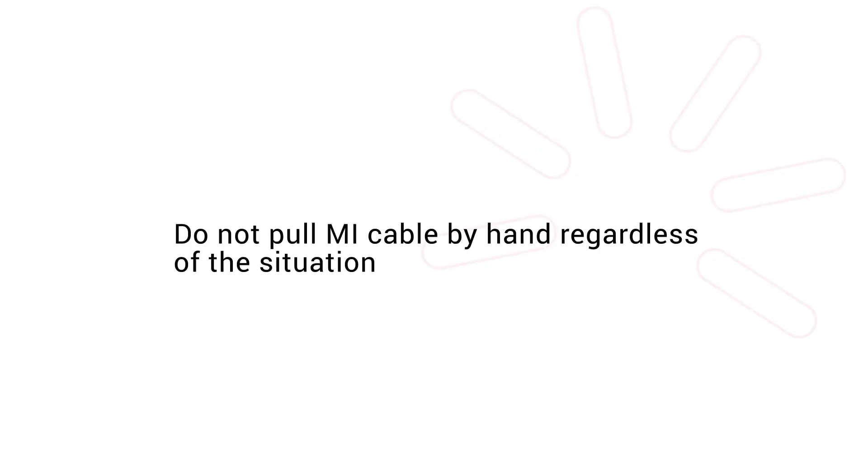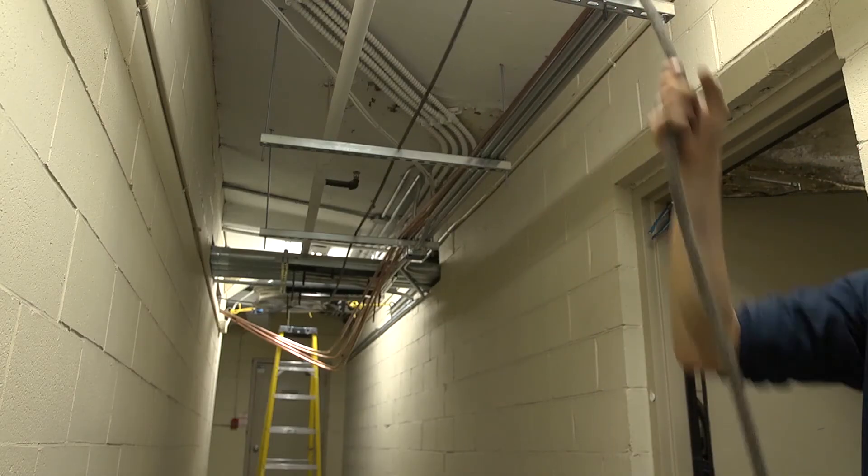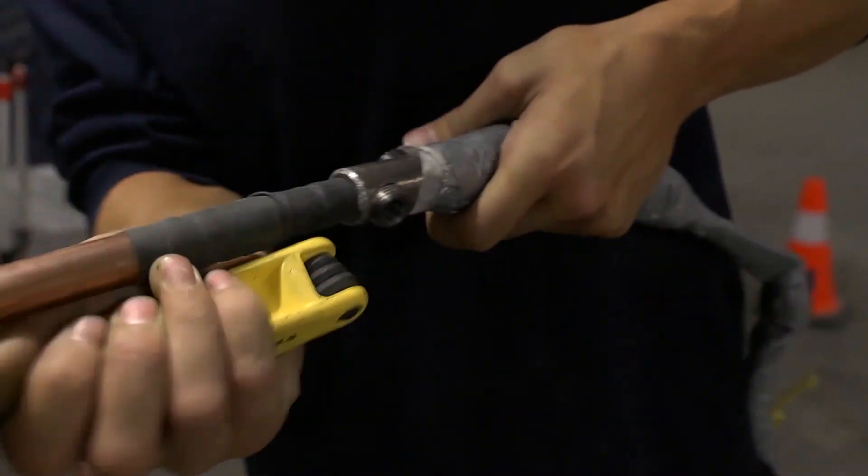When it comes to pulling MI cable, you need to make sure the proper setup has been completed. You can go back to the previous section of this video to see a step-by-step guide on how to do that. nVent does not recommend and strongly advises against pulling cable by hand no matter the scenario. Doing so will make the cable pull extremely difficult, if not impossible, and the results will be far from ideal as the cable will end up with a lot of waves in it and become very hard and time consuming to dress up and tie securely to the building structure. Start by checking that the rope has been properly fed through the cable run and attached with a swivel head onto the head of the cable.